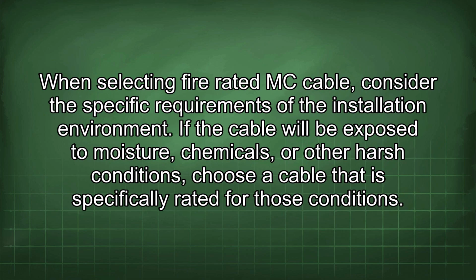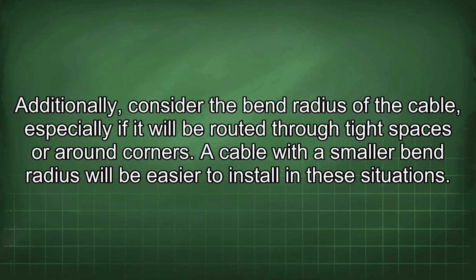When selecting fire-rated MC cable, consider the specific requirements of the installation environment. If the cable will be exposed to moisture, chemicals, or other harsh conditions, choose a cable that is specifically rated for those conditions. Additionally, consider the bend radius of the cable, especially if it will be routed through tight spaces or around corners. A cable with a smaller bend radius will be easier to install in these situations.